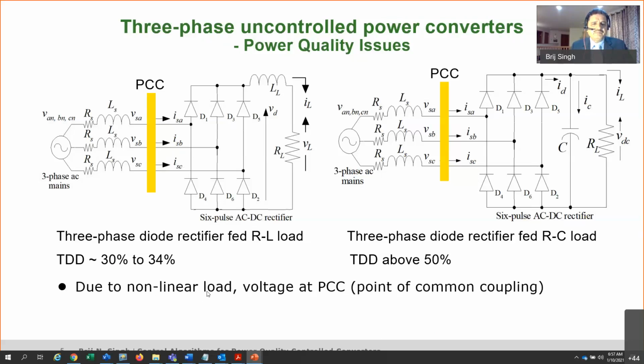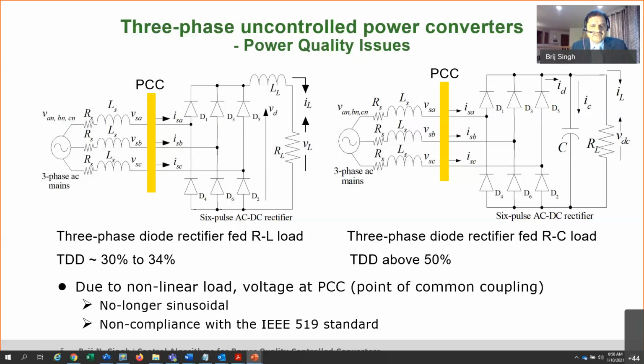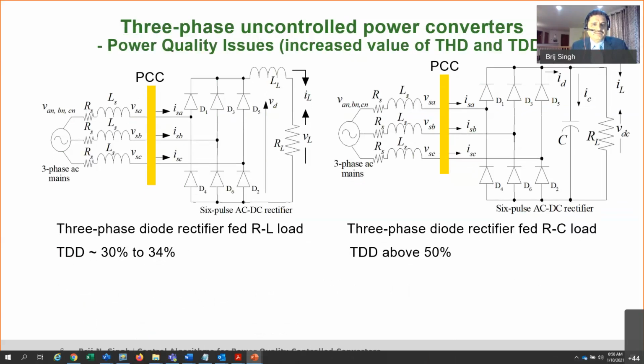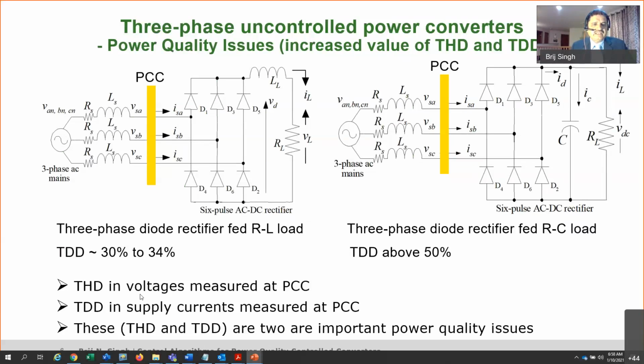Means if the waveform shape changes with the load, as you vary this load, and the voltage waveform shape changes at this point PCC, then you are generating harmonics and you are a nonlinear load. So no longer sinusoidal, non-compliant with IEEE 519 standard. So what does it do basically? THD is measured in the voltage and TDD is measured in the supply current. So both are measured harmonics, but harmonic in the voltage is called THD, total harmonic distortion, and harmonic in the current produced by your load is called TDD, total demand distortion.